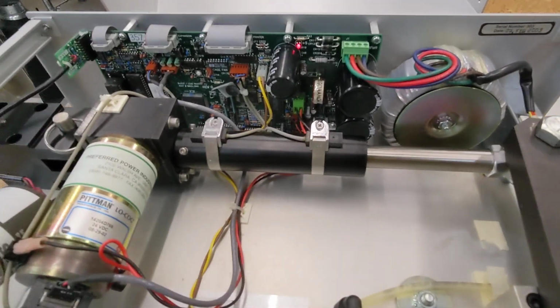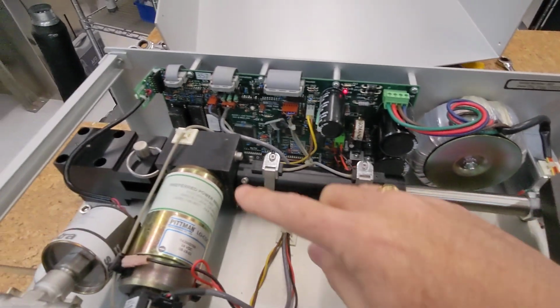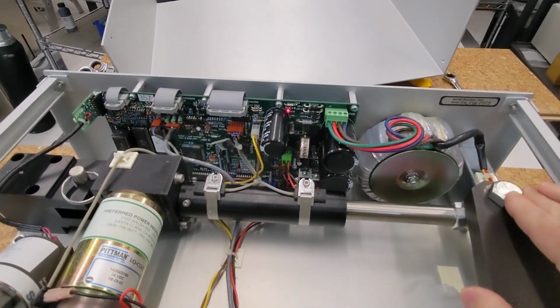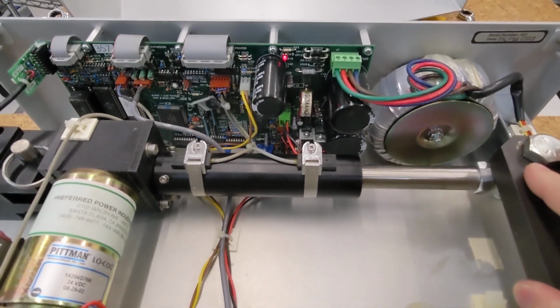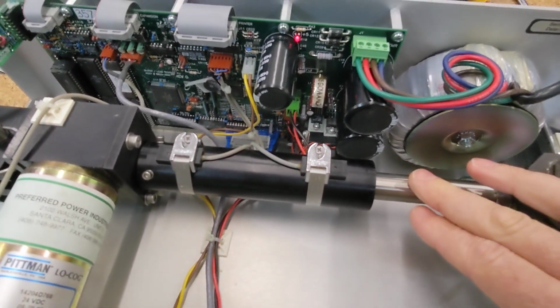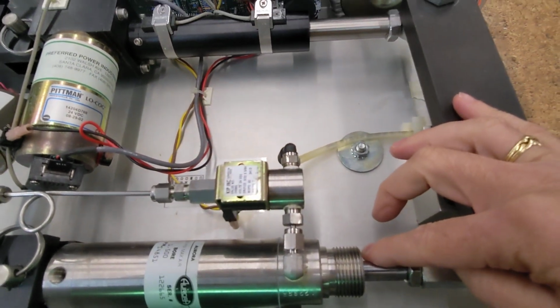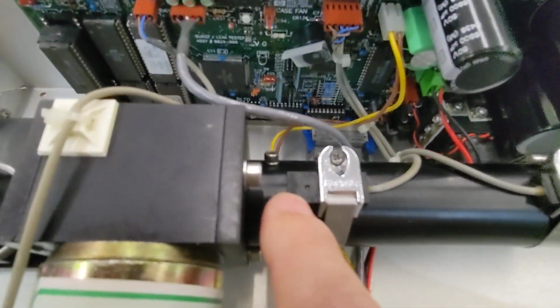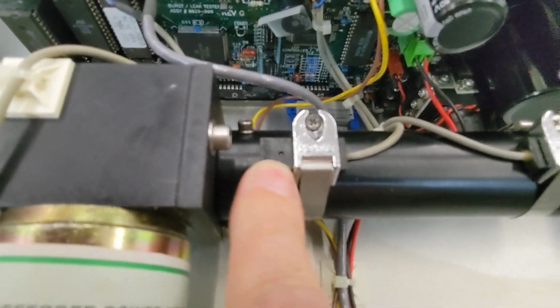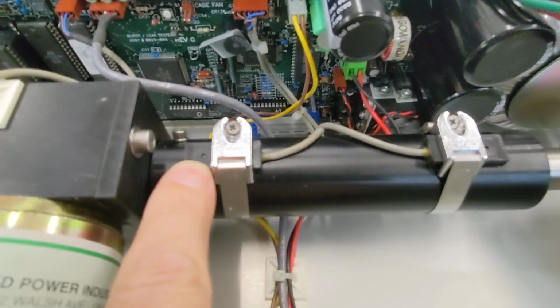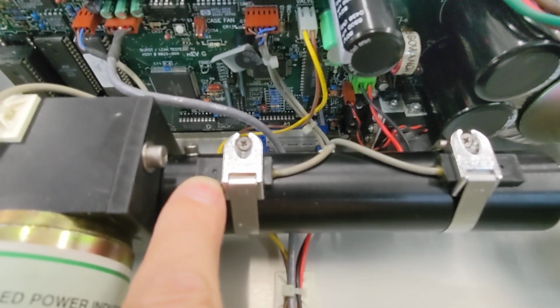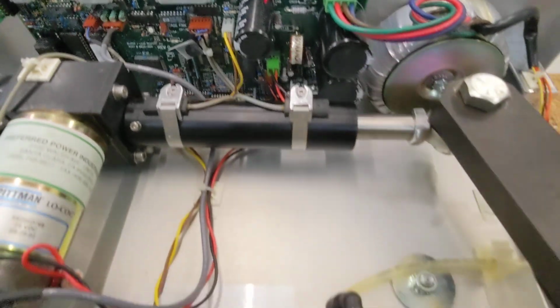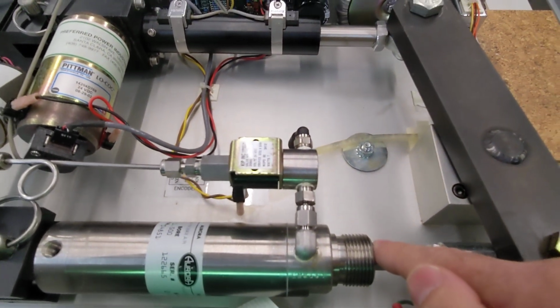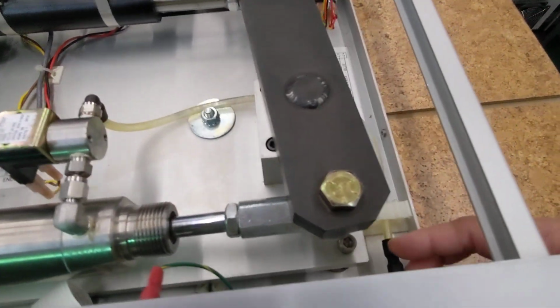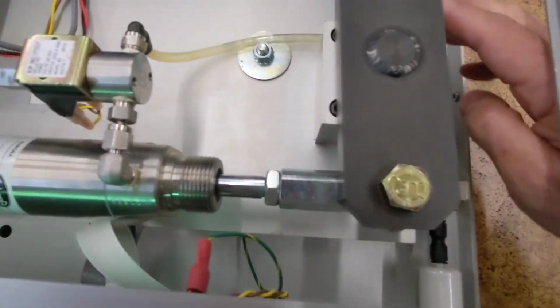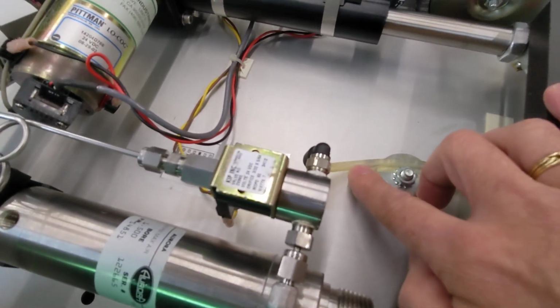You probably don't hear the high-pitched noise, but there's definitely a switching frequency controlling this motor, pretty low so it's audible even to me with my old ears. So this is now retracting, and this is extending, and it's going to retract until that LED comes on, which won't be too long. Here's both LEDs, and it won't stay on for long. There it is, and now it's extending, meaning this is in the aspiration or intake phase, drawing liquid in from here, from this filter area, up through this tube. You can maybe see little bubbles shooting up there.